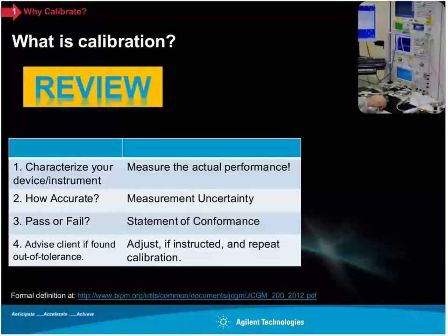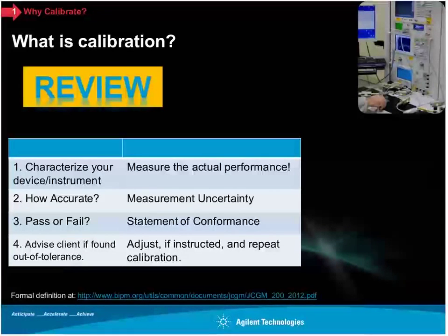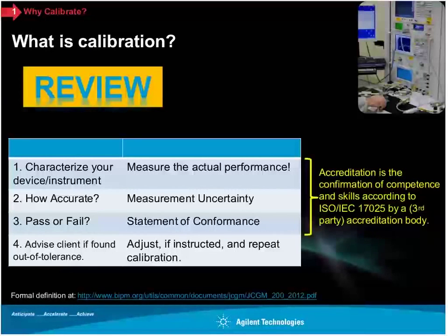Now then, if you actually observe that, oh, gee, we're sorry, but your instrument failed the specification, it was out of specification, in that case, 17025 says you're supposed to advise the client if you find it out of tolerance. And at Agilent Technologies, what we do is that we will normally, unless we're instructed otherwise, go ahead and adjust the instrument, repeat the calibration, and then provide a second set of data. So that's kind of a review of what the calibration process is.